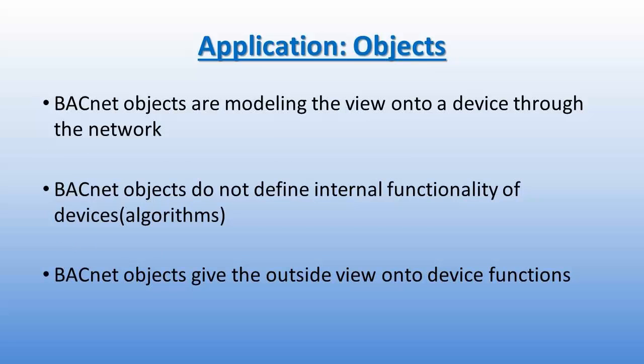In BACnet, objects model the view onto a device through the network. Objects do not define the internal function of the devices — the algorithms in this case — but rather give an outside view onto device functions. For example, the BACnet loop object is defined in such a way that different loop algorithms — PI, PID, sequence, and predictive control — can all be mapped.